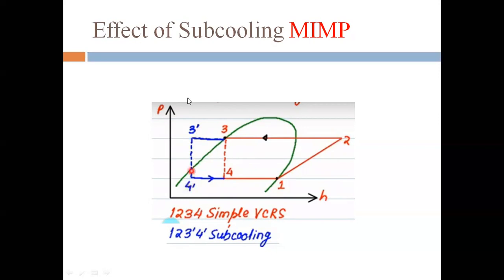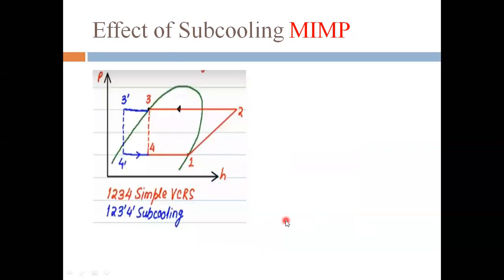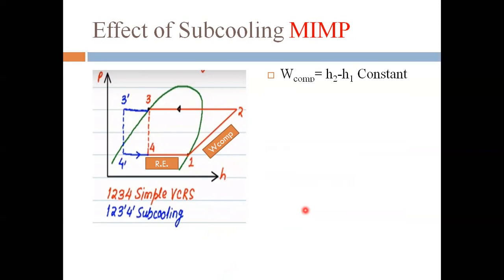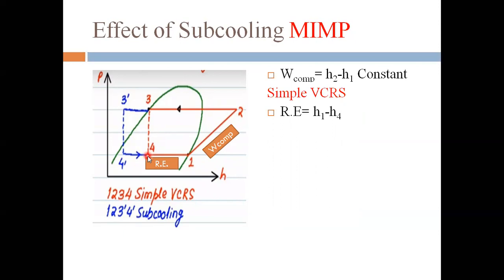The new cycle with sub-cooling is one, two, three-dash, four-dash. We need to understand whether COP is increasing, decreasing, or remaining constant. The refrigerating effect region and the compression work W are already identified. By doing sub-cooling, we are not changing any pressure, so the compression work W = h2 − h1 remains constant. In the simple VCRS, the refrigerating effect is h1 − h4.